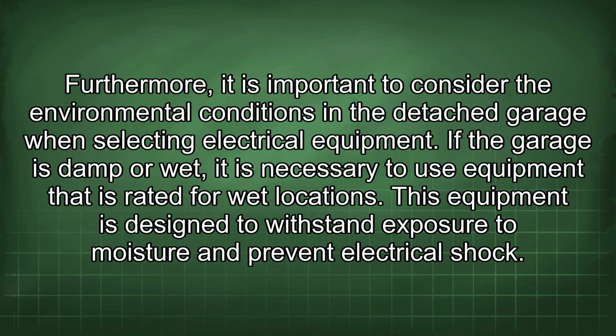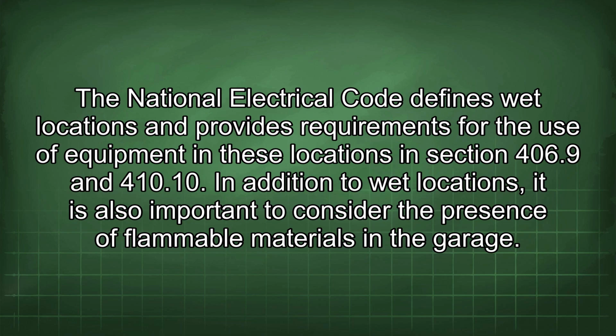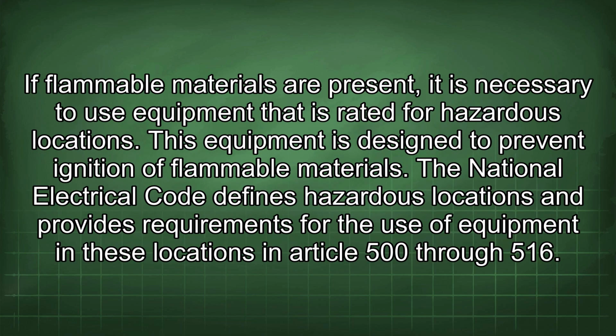Furthermore, it is important to consider the environmental conditions in the detached garage when selecting electrical equipment. If the garage is damp or wet, it is necessary to use equipment that is rated for wet locations. This equipment is designed to withstand exposure to moisture and prevent electrical shock. The National Electrical Code defines wet locations and provides requirements for the use of equipment in these locations in Section 406.9 and 410.10. In addition to wet locations, it is also important to consider the presence of flammable materials in the garage. If flammable materials are present, it is necessary to use equipment that is rated for hazardous locations. This equipment is designed to prevent ignition of flammable materials.